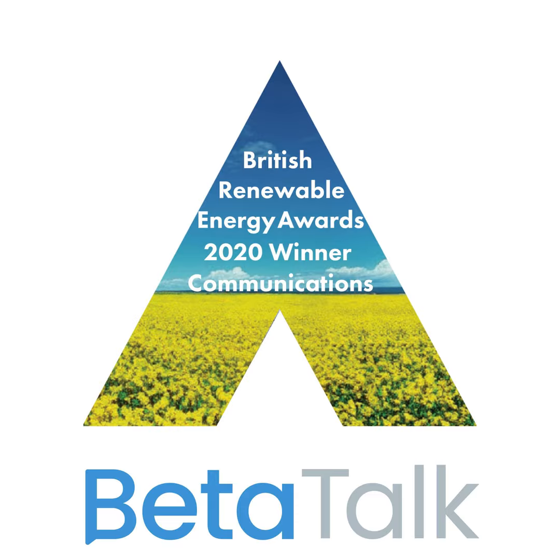But when it starts... there's some really good BMS companies out there. It sounds like I'm slating them, but there's been some atrocious ones where we've gone in and looked at issues, and you've gone, oh my god, the heat pump's cycling every 2 minutes, doing simultaneous heat and cooling, having no thermal stores. It was a disaster on the design, not just the BMS but everything. Then you have to go in and sort of say, I'm really sorry, but we have to start again.